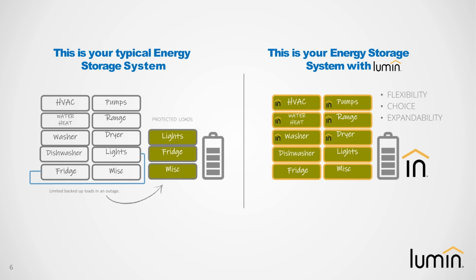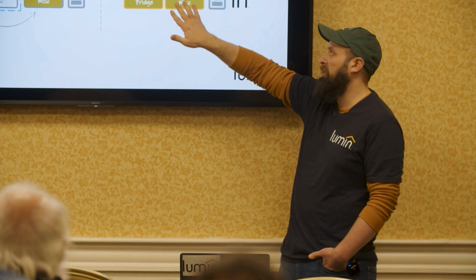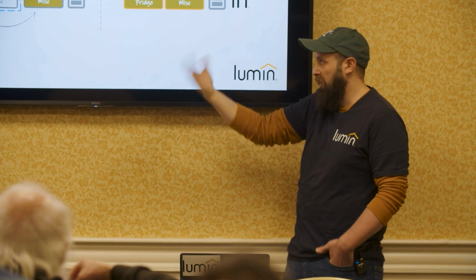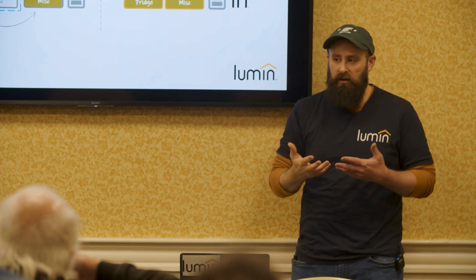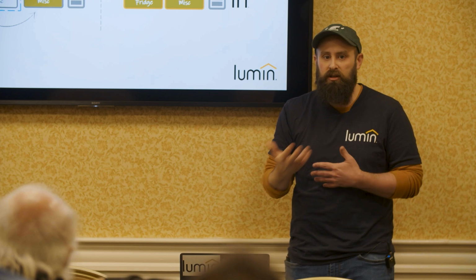What we're doing with the Lumin panel is to not connect to the lighter loads, but have the ability to shed at the moment of outage all of those heavy loads. So they would all come off, and what's left in the main service panel is going to be your light loads. That being said, if you want to utilize those heavy loads, you have the ability through software to do so, so you can control that relay at will.